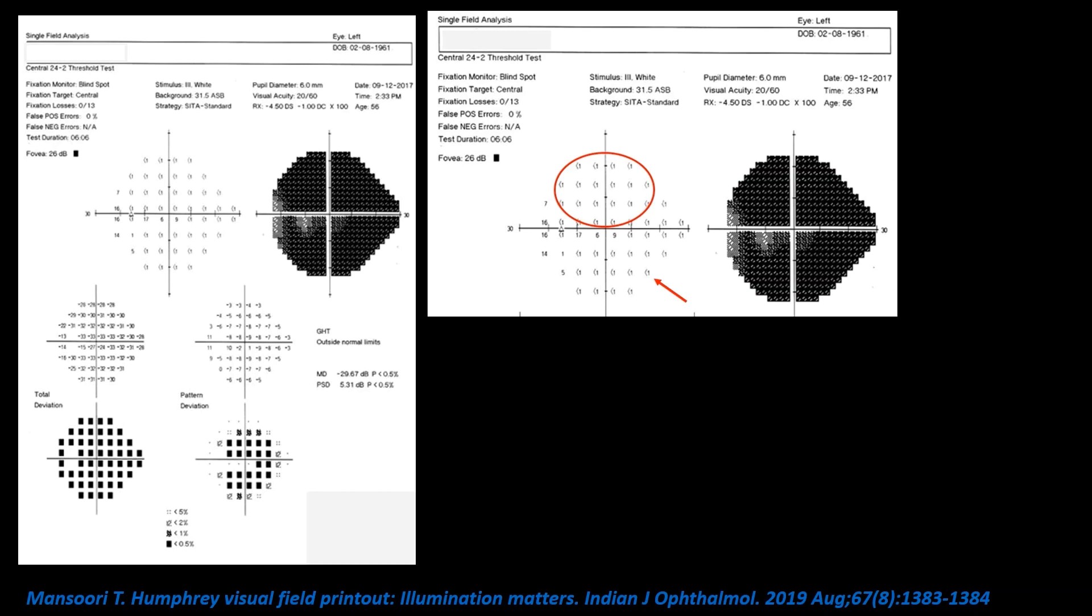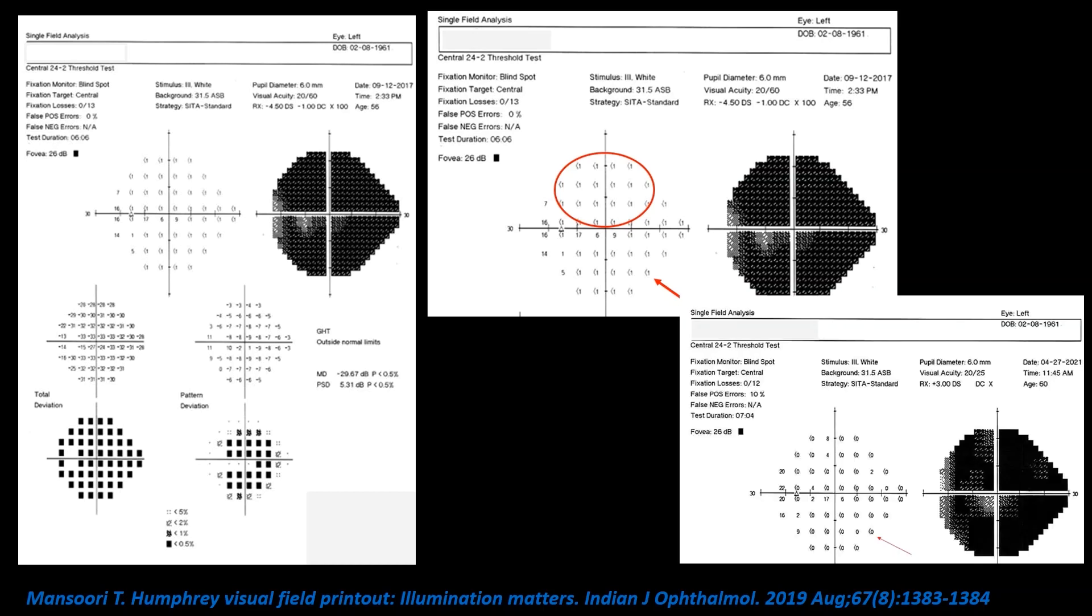Grayscale does not show black areas but a level of gray as the scotoma falls in different bandwidth range. This occurs when the light bulb is dim, and replacement of the bulb rectifies the loss of brightness range.